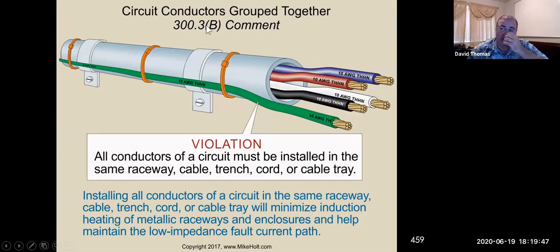Circuit conductors that are grouped together need to go into the same conduit. So this is a violation by running the ground on the outside. You can't do that. When we're installing all conductors in the circuit in the same raceway, trench, cord, whatever, cable tray, we minimize induction heat in metallic raceways and enclosures and help maintain a low impedance fault current pathway. And so those would need to be inside the conduit in this case.